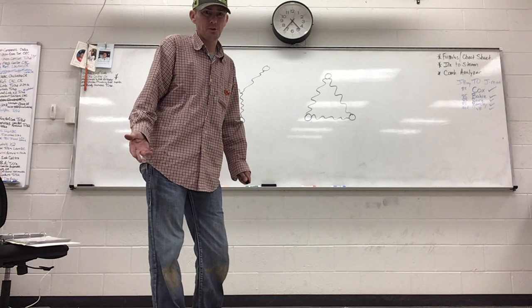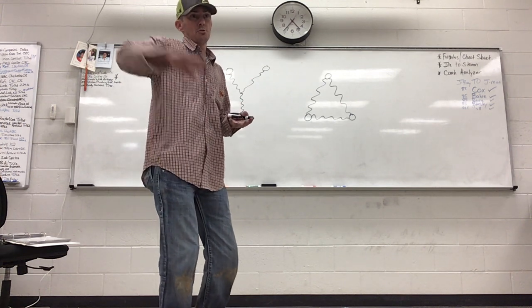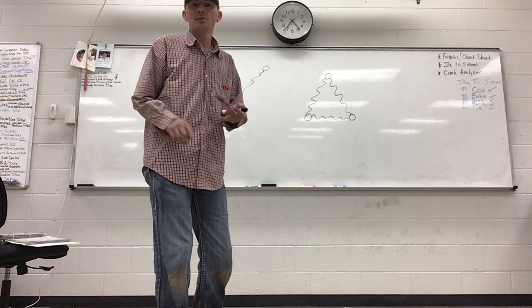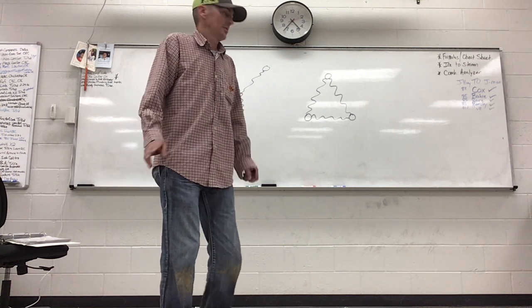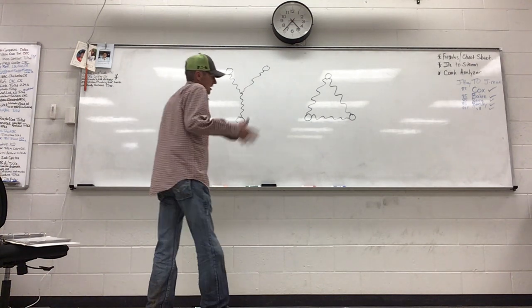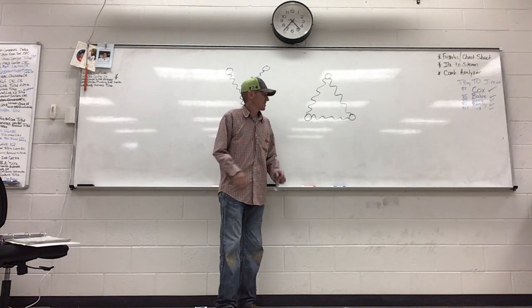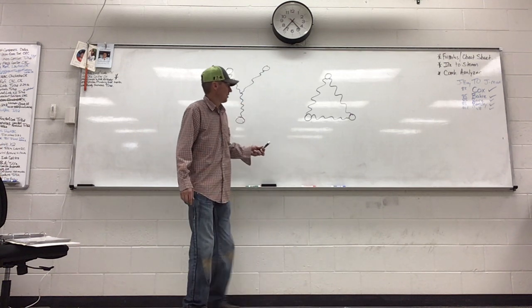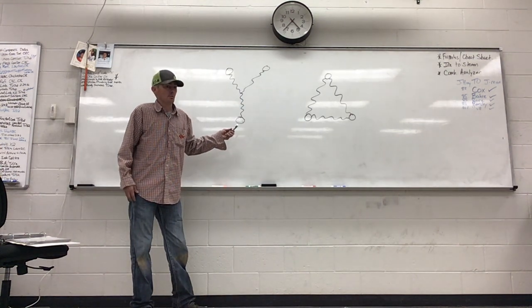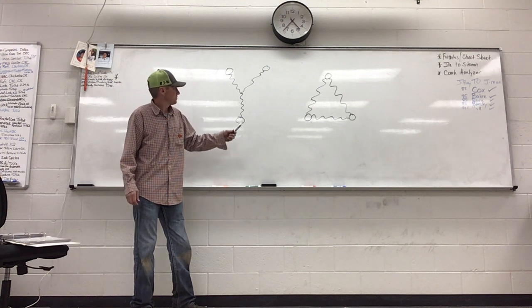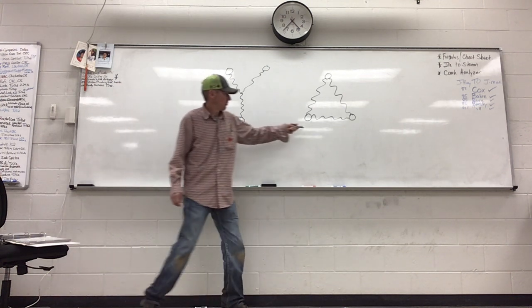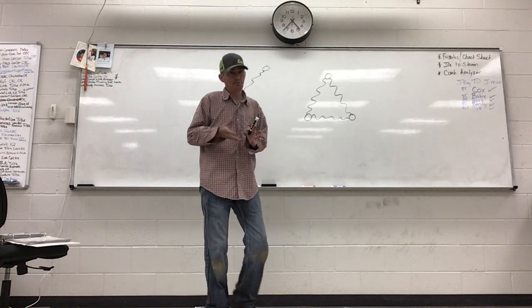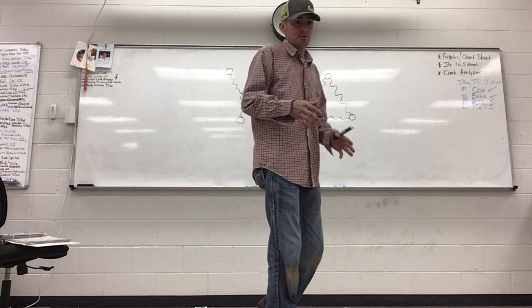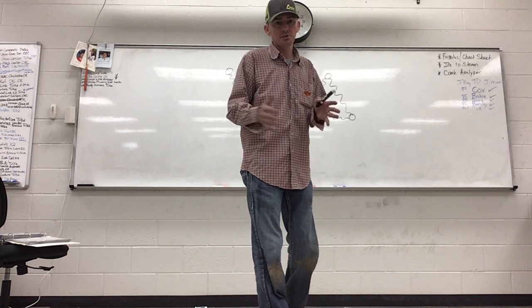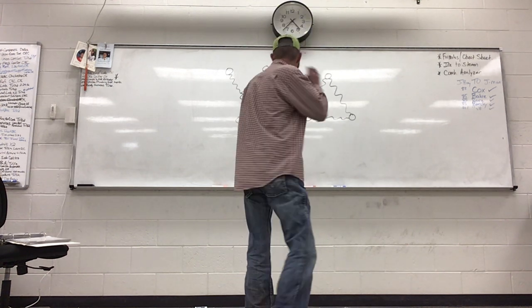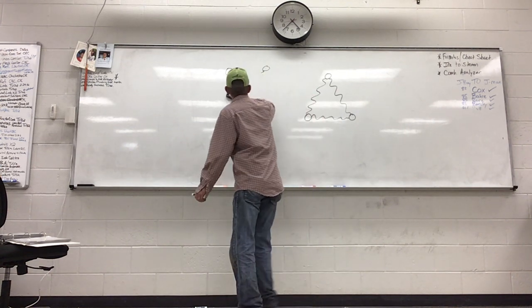So in today's world, we'd probably put it on a drive, on a VFD, and we would do a ramp. And you know, the name of the game is bring it on, leave it on, match the capacity, all that good stuff. We don't want to cycle anything off and on. We want to bring it on and leave it on. Startups kill compressors. But anyway, we're going to get into centrifugals that aren't on a drive. Some of the older stuff is going to start as a Y, run as a delta, and then we'll use inlet guide vanes to vary the capacity. Basically, inlet guide vanes on a centrifugal are just going to block the suction gas coming in, and that's how you vary the capacity on a centrifugal.